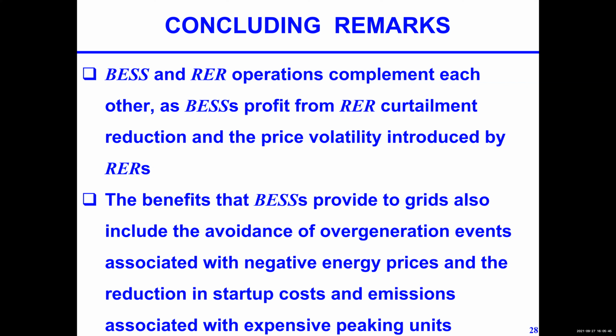Well, it bothers me with those results, Phil, that as you increase the size on a per megawatt basis, you're decreasing your profits. So there's absolutely no incentive not to have 450 megawatt units as opposed to having a 200 megawatt unit. Right, so some of that analysis needs to be built in.